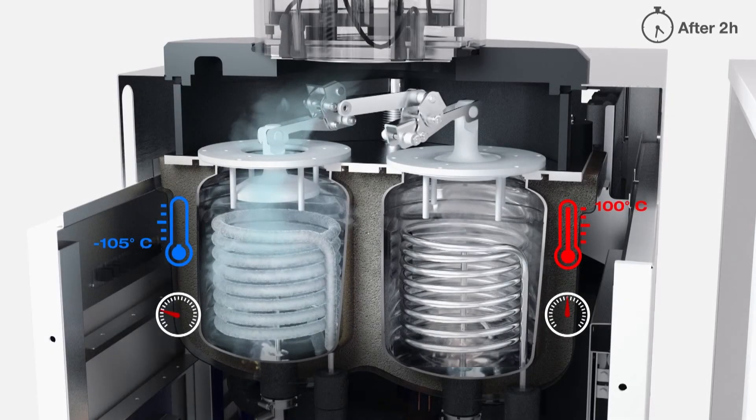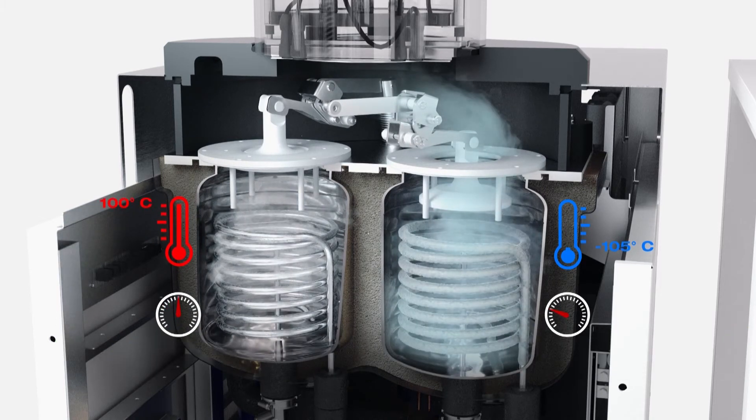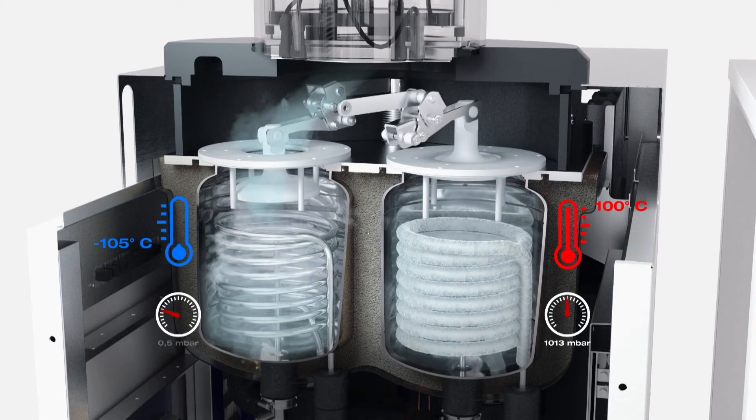What makes the Büchi Lyovapor L-300 unique is the use of dual condensers. Whilst one condenser is involved in the lyophilisation process, the other is being defrosted and cleaned.